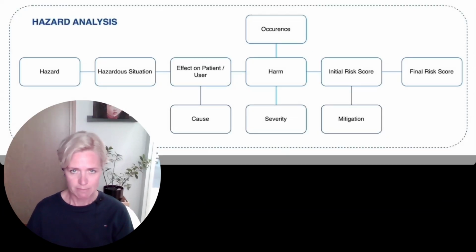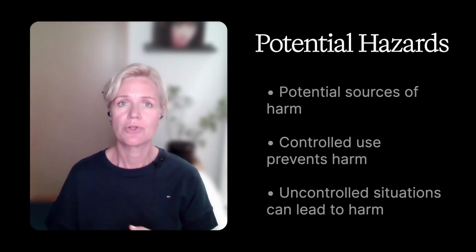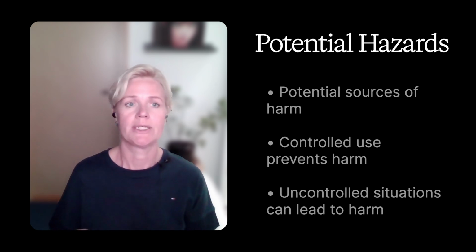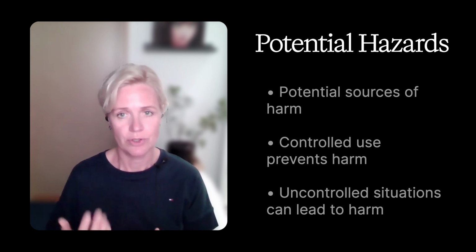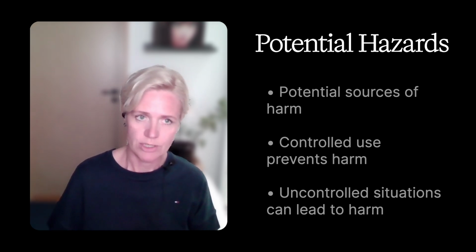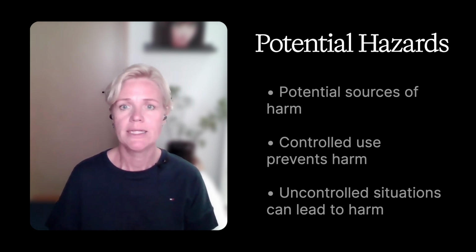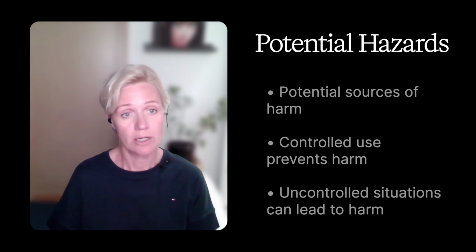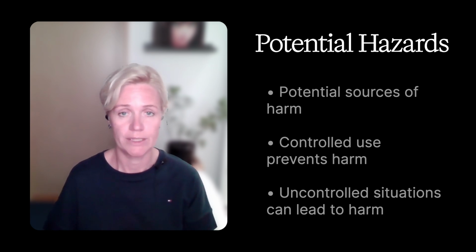In terms of risk analysis methods, you will have to do hazard analysis as a bare minimum. Hazard analysis is a top-down risk management method looking at a medical device, hazards, hazardous situations, and harms that these hazards can cause. But what is hazard? Hazard itself is a potential source of harm, and there are a lot of hazards around us that will not harm anybody as long as the medical devices are used in controlled manner. But uncontrolled situations or certain sequences of events may lead to potentially hazardous situations where hazards can be realized, and they could cause harm to the users and patients when they're realized.